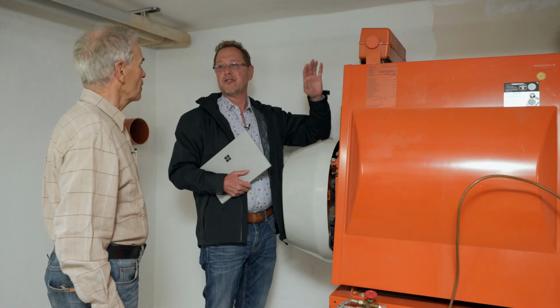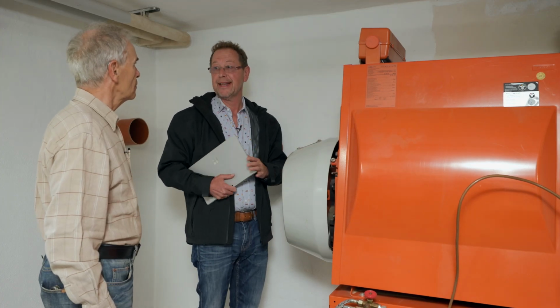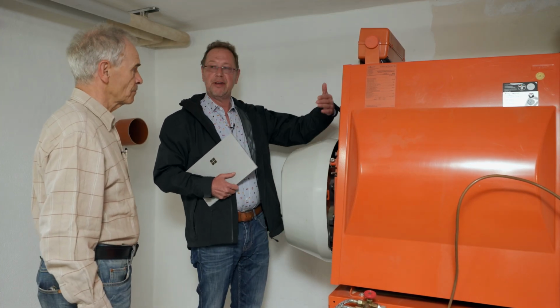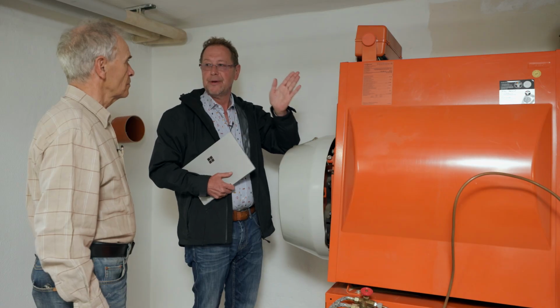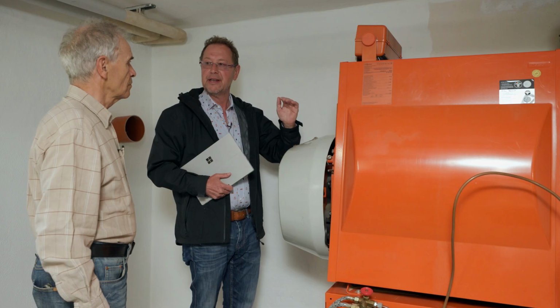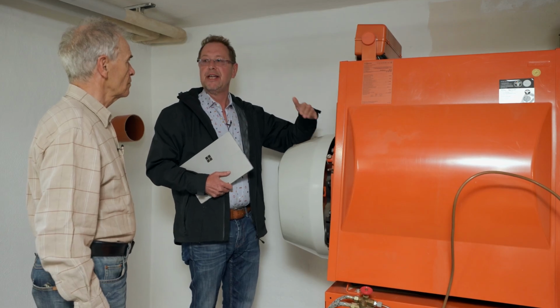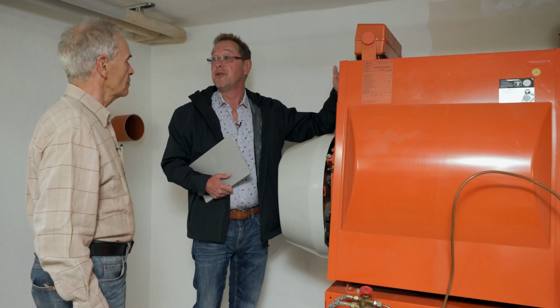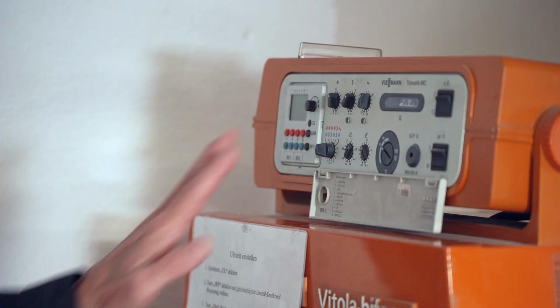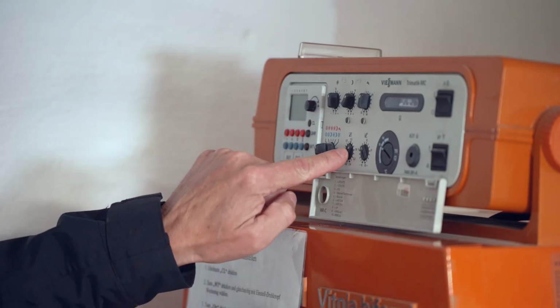This machine can't record any temperatures, so you'll have to keep a journal. What that means is, in the winter, you write down the outside temperature on a piece of paper, and do the same with the thermometer on the heater. This will give you the flow temperature from inside to outside. I'll need that information from you when the winter is over, and I can use it to calibrate the new heat pump system. The concept behind it is simple.